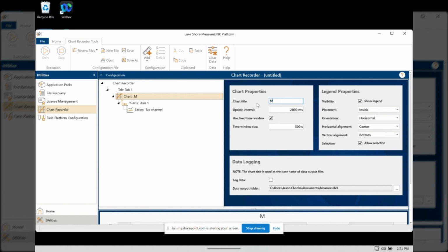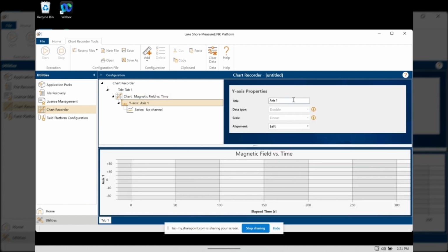So this is going to be magnetic field strength versus time. And you'll see, we can give the chart title, any title we want. We can also set the update interval. I think it's 300 milliseconds total, but we're going to collect data on half-second intervals, so 500 milliseconds. And we'll change this axis to magnetic field strength. And this could be Tesla, this could be Gauss. Really, these are all user-defined, so you can make them whatever you'd like.